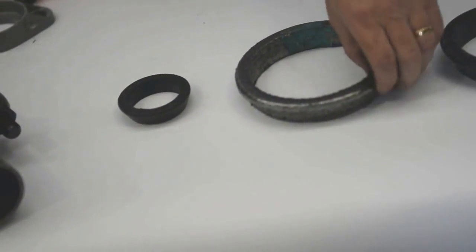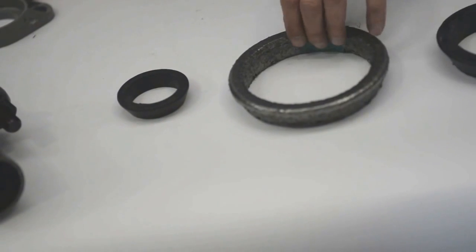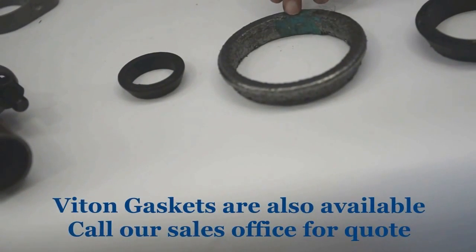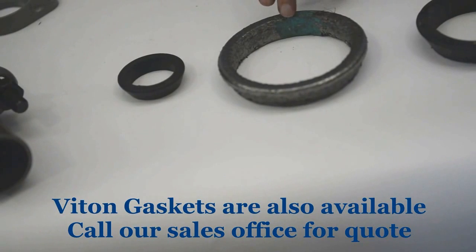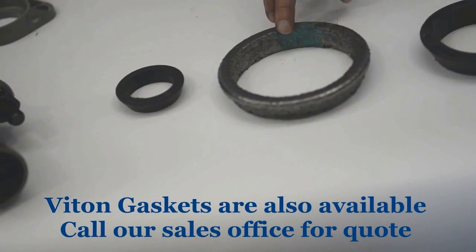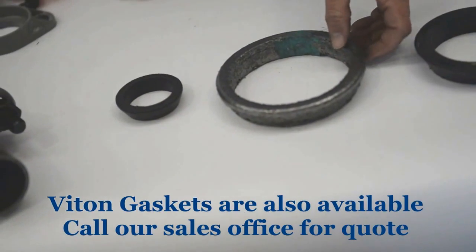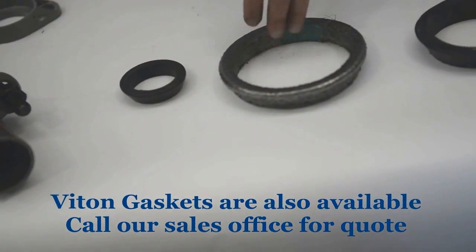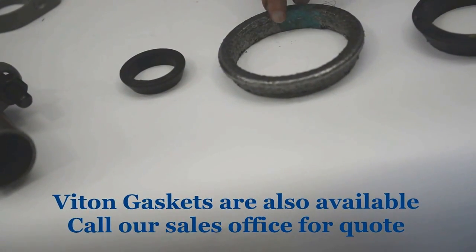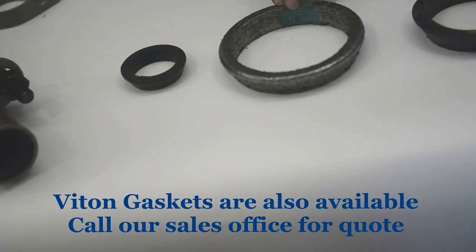Because of the braided cloth, the nature of the gasket, it will not create an airtight seal. It may have some slight leakage to it, but that's just the nature of the type of gasket and the application that it's used in. Low pressure steam is the normal application for this gasket.